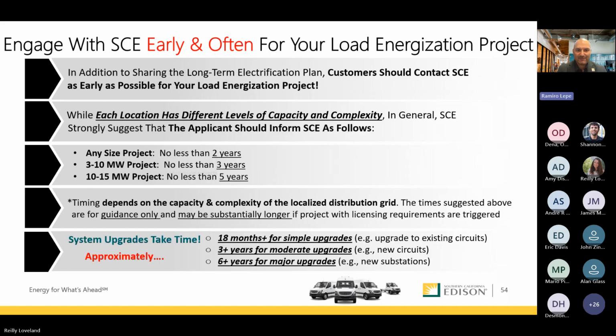So, time frame. Engage with us as early as possible on your project, but as a rule of thumb — right there in the middle you can see 'any size project' — here's the timeline for when you should reach out to us. If you have a project of any size, it needs to be at least 2 years out. If you're looking at a 3 to 10 megawatt project, which isn't usually as likely for school districts, we're looking at a minimum of 3 years, and anything 10 megawatts or above in demand, we definitely want engagement no less than 5 years out.